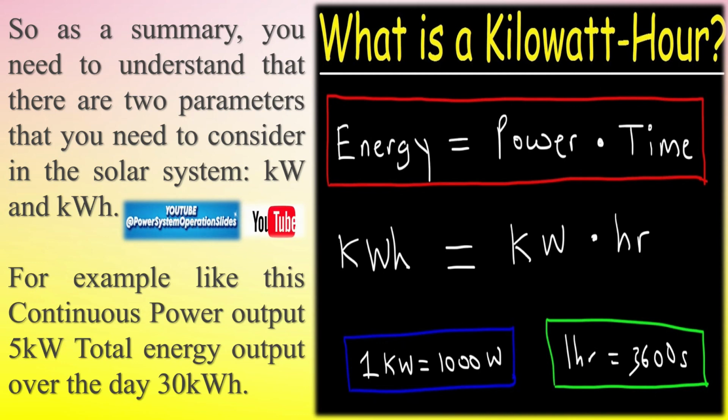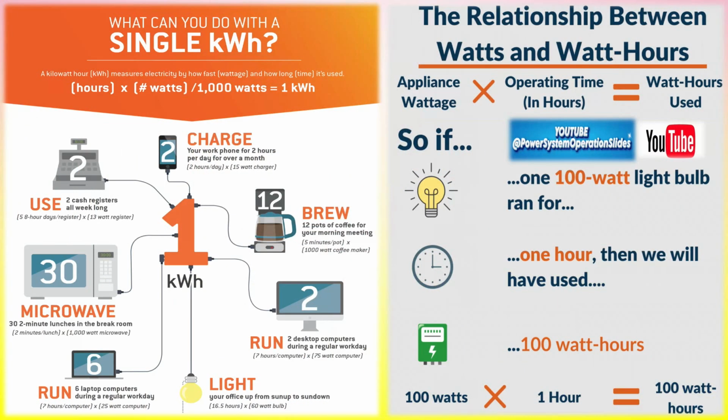Reactive power, kVAR, is the portion of power that does no useful work but is necessary to maintain voltage levels in the system. Apparent power, kVA, is the combination of real and reactive power. A poor power factor can lead to inefficiencies, and industries with low power factors may face higher costs. Power factor correction devices like capacitors are used to improve power factor and reduce wasted energy.